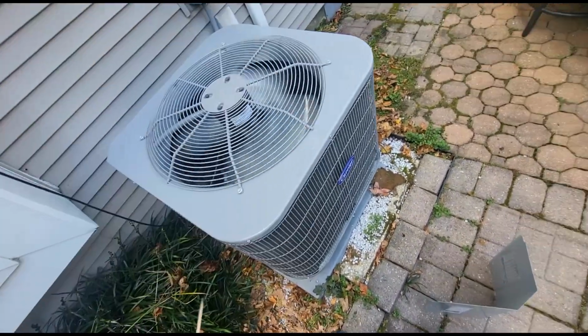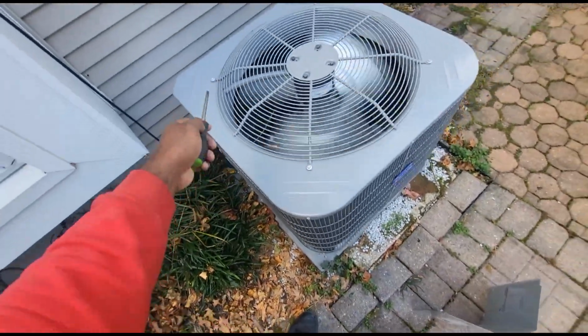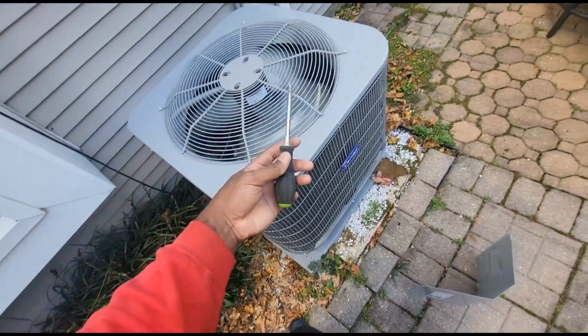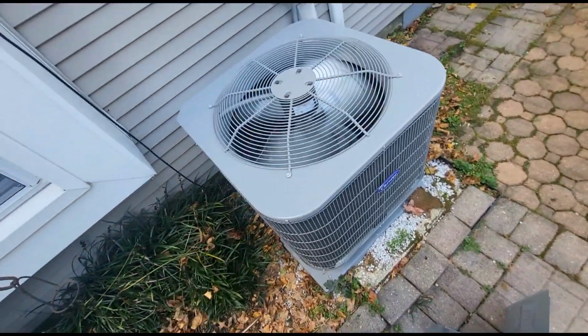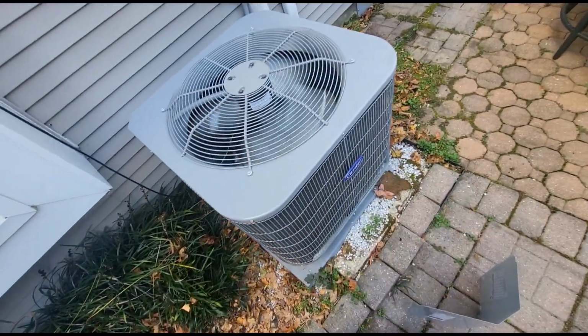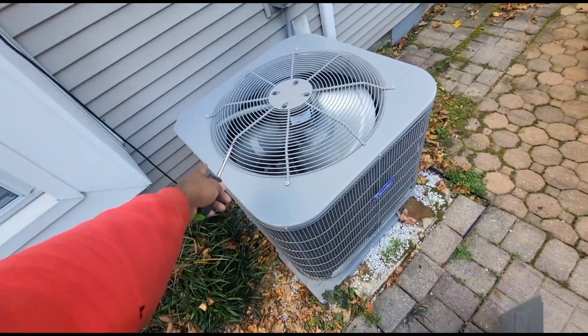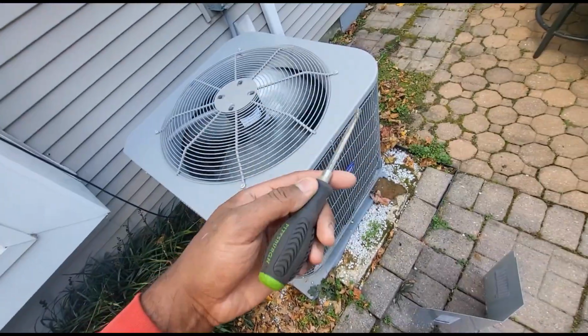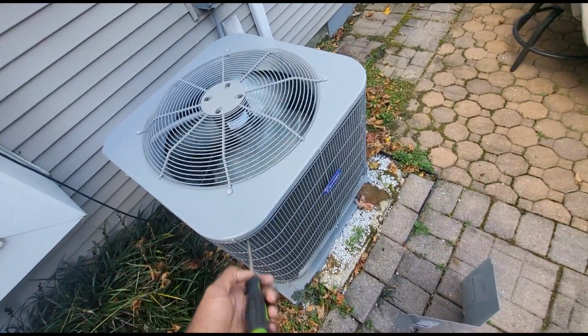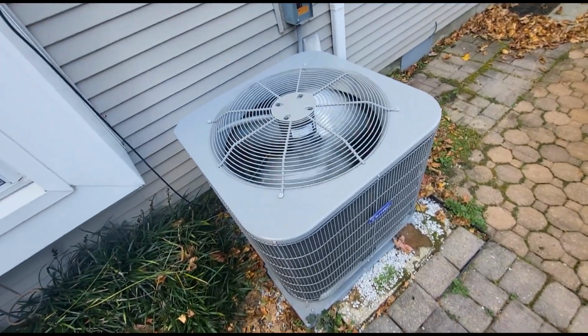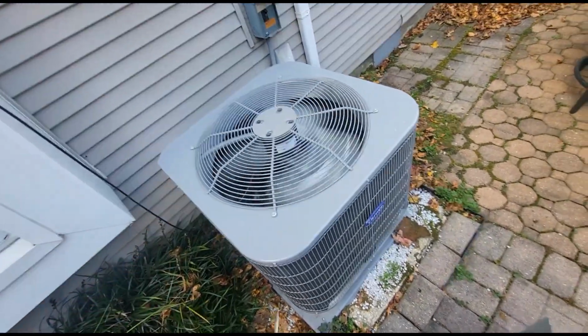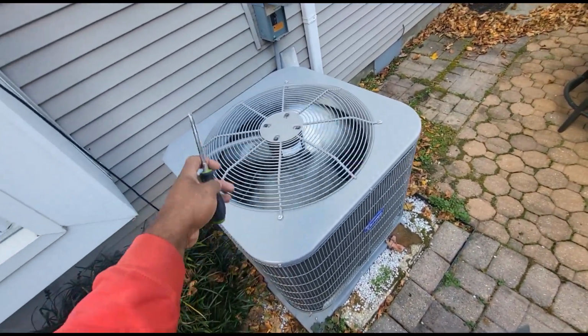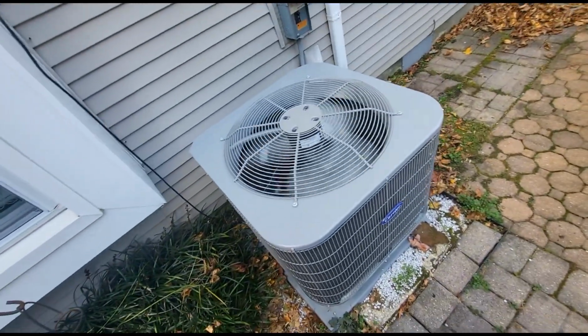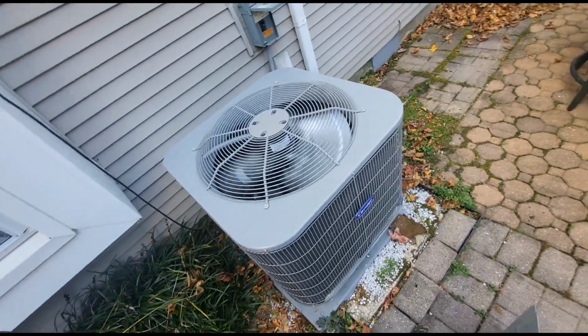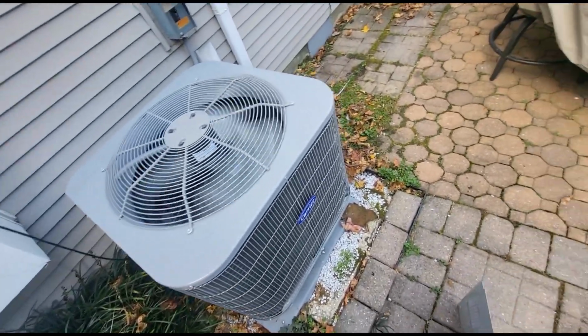So guys, a lot can happen on the heat pump if the defrost board fails. That's why you always have to be preventative and make sure you test these on every maintenance. It takes about 2 seconds. Take your time. If the defrost doesn't engage within a couple of seconds of you jumping out the pins, this is something you need to bring to the customer's attention about what could happen, even if, once again, the heat pump is still working. If that defrost doesn't fully engage, then this is going to spell a nightmare down the line.